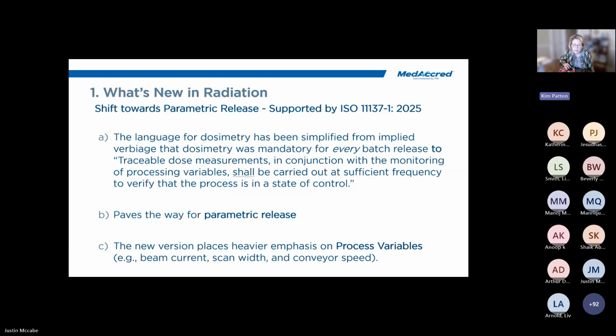The previous version implied that routine dosimetry was the primary evidence for product release, and the new version modifies this to where, if controlled and monitored, the physical placement of dosimeters on every single batch may no longer be the sole requirement for release.